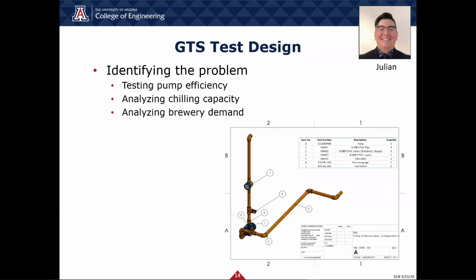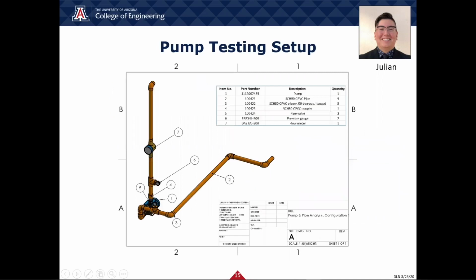Designing the GTS, we identified the 3 areas of concern as the pump efficiency, the chilling capacity, and the chilling demand of the brewery. The solutions for these problems were to be delivered to the sponsor in the form of a final report. Here you can see one of the testing configurations for the pump efficiency test involving a flow meter, pressure gauges, and a multimeter.